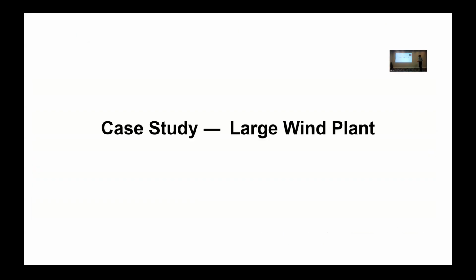Now I move on to a large wind plant study. We did a number of simulations using EMTP. It involved line energization, transformer energization, inrush current, cap bank switching, and also TRV and harmonic studies using EMTP. However, this presentation is only about zero sequence resonance. And by the way, this was the first time we ran this study of zero sequence resonance.